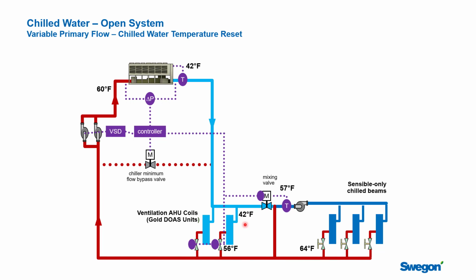And any savings you get by resetting the chilled water temperature, if you can't do the cooling, then all the local cooling devices are going to respond by saying, hey, you're giving me warmer water, I can't get the cooling done in my zone, so I'm going to open my chilled water valve and consume more water. So while you may be saving energy up here in your refrigeration plants because they can make warmer water, which is easier, you may actually spend that energy over here increasing the flow rates out to all the devices, so you have to be really careful how you do that. And ultimately, the most important thing is to maintain good dehumidification control at your primary air handling units.